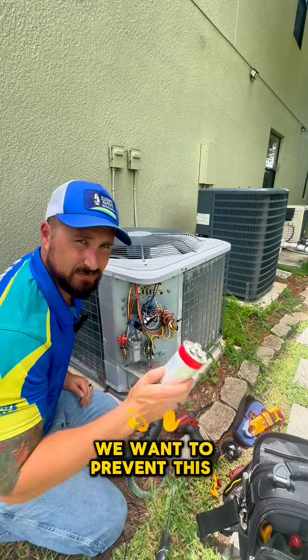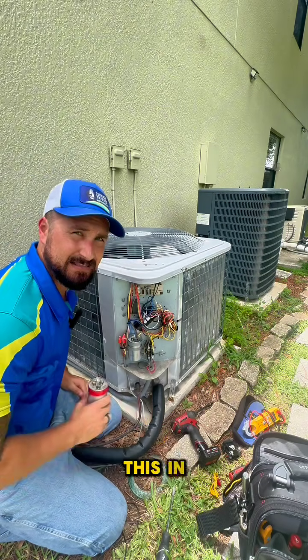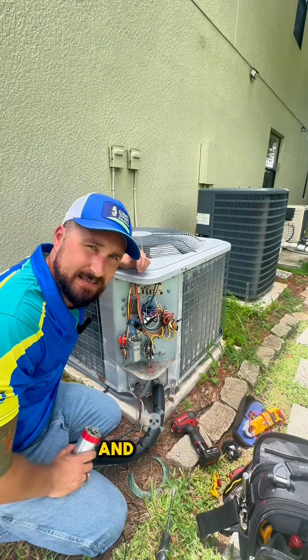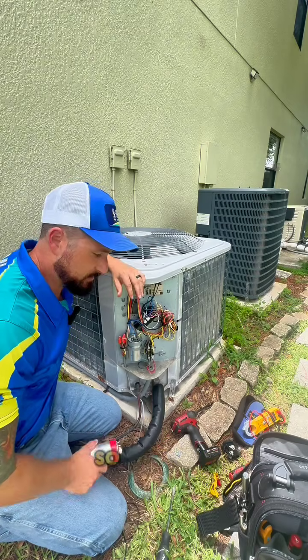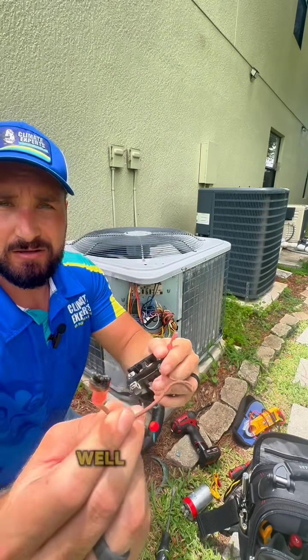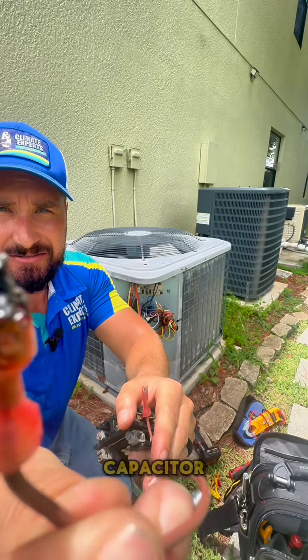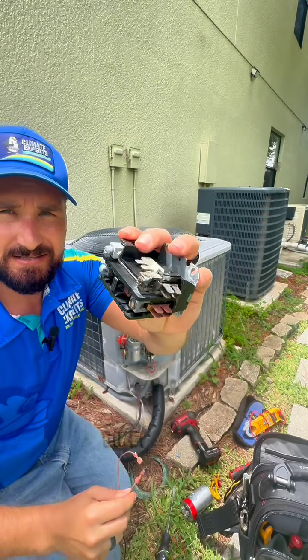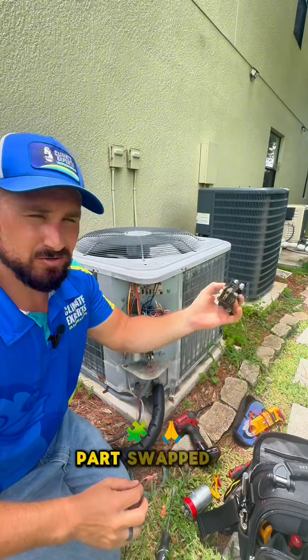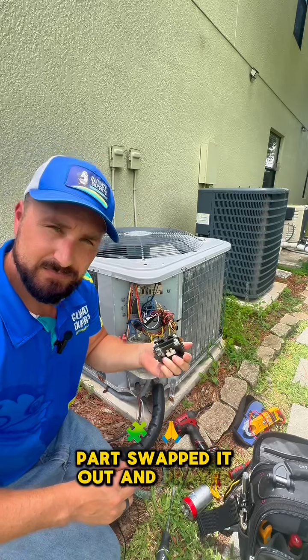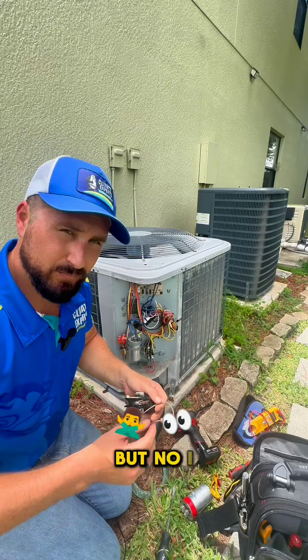We want to prevent this from failing again. We don't want to just throw this in and then something else is going on and it kills your compressor, it kills your fan motor. So I noticed this wire as well, right here, sticking on the capacitor. Now, I could have just replaced this like some technicians would have done, part swapped it out and prayed that it worked. But no, I looked further.